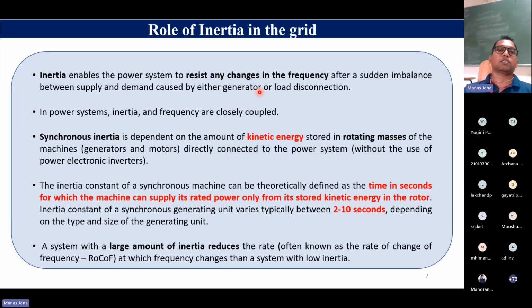The first aspect is inertia. What is inertia? In the layman perspective, it is nothing but resistance to change. So in the power system perspective, what is that resistance to change in? This is nothing but the change in frequency after any contingency. So if in our grid we have very nice inertia, and following any contingency, either a large generation loss or a large load loss, that will help to arrest the frequency deviation.